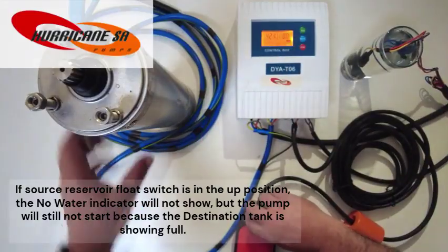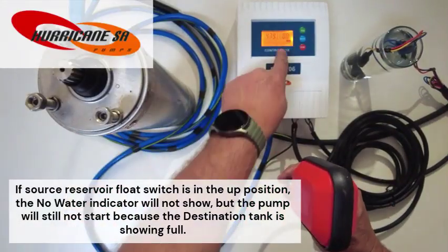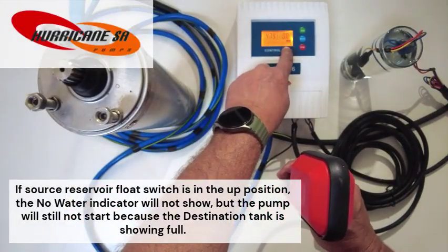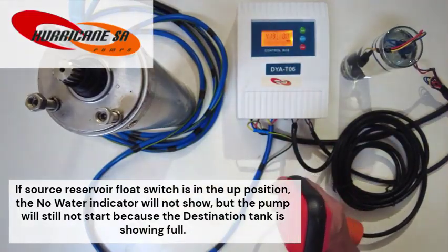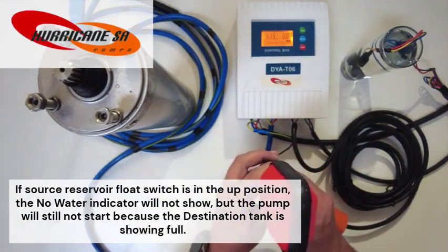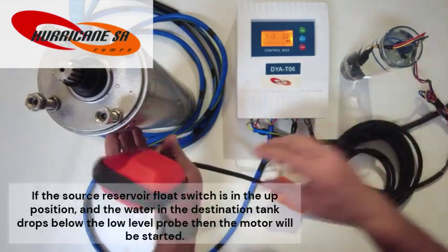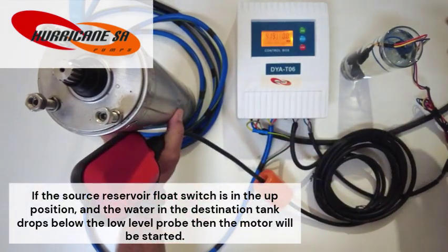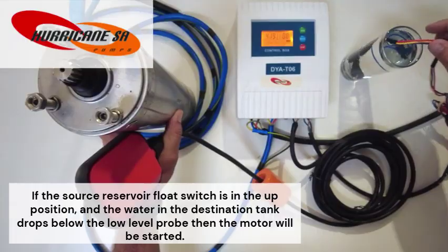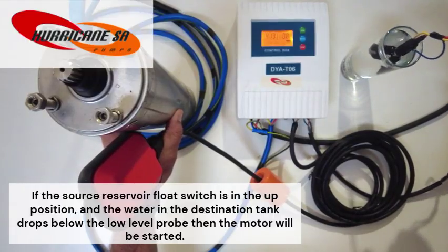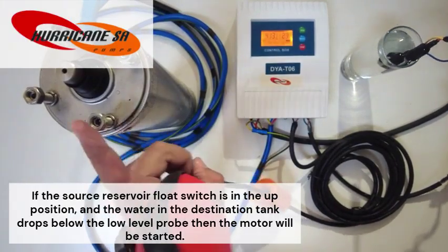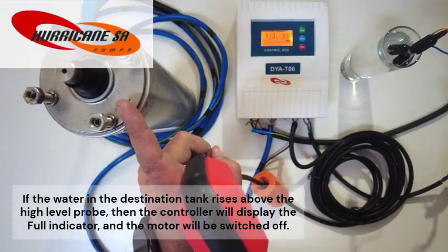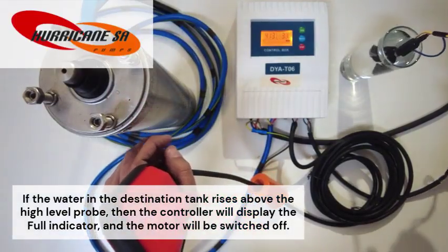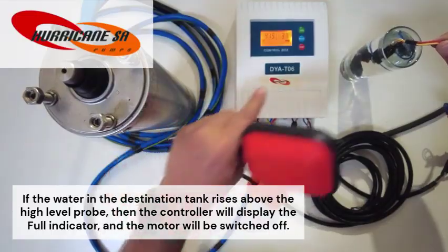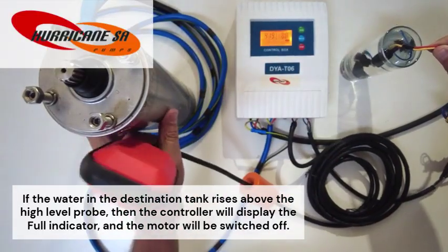If the source reservoir float switch is in the up position, the no water indicator will not show, but the pump will still not start because the destination tank is showing full. If the source reservoir float switch is in the up position and the water in the destination tank drops below the low level probe, then the motor will be started. If the water in the destination tank rises above the high level probe, then the controller will display the full indicator and the motor will be switched off.